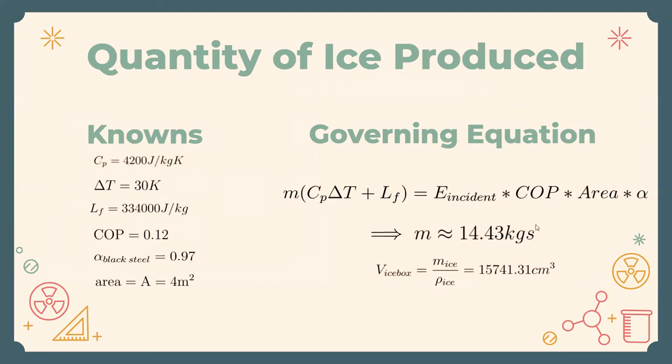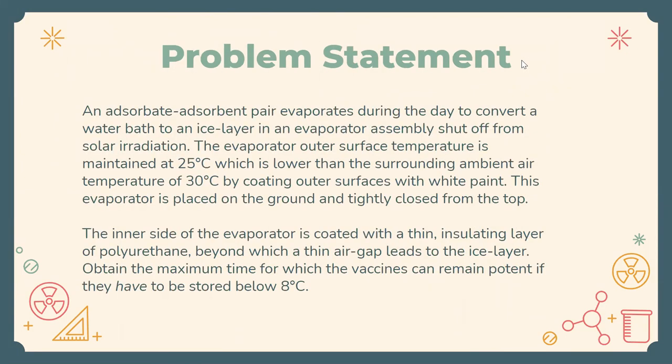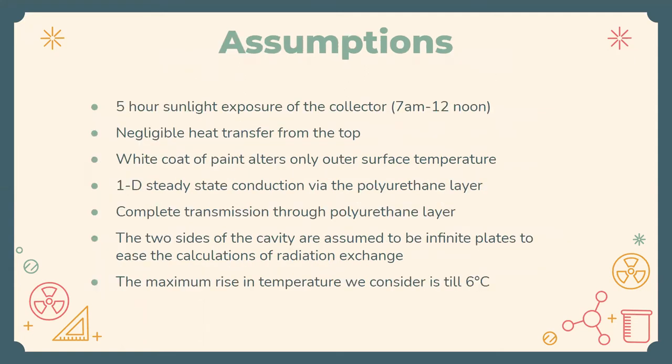Having completed our view of the collector, we now move on to the evaporator. The problem statement for the evaporator is as follows: the adsorbent pair evaporates during the day to convert a water bath to an ice layer. The evaporator outer surface is maintained at 25 degrees Celsius by coating with white paint. The air temperature is ambient at 30 degrees. The inner side of the evaporator is coated with a thin insulating layer of polyurethane, beyond which we have a thin air gap leading to the ice box. Our objective at the end of this section would be to calculate the maximum time for which the vaccines can remain potent if they have to be stored below 8 degrees Celsius.